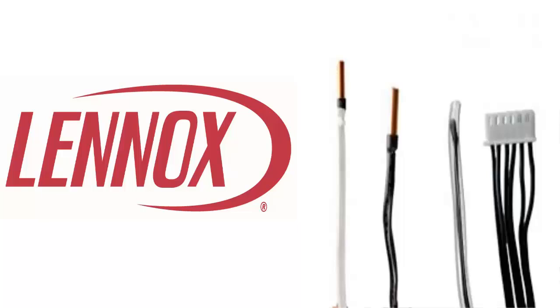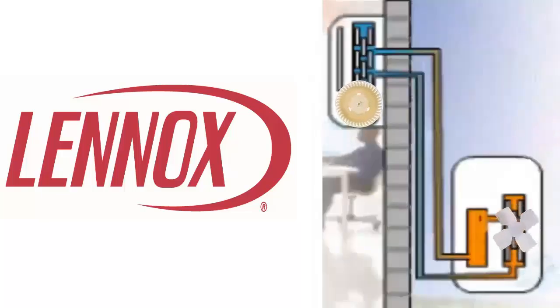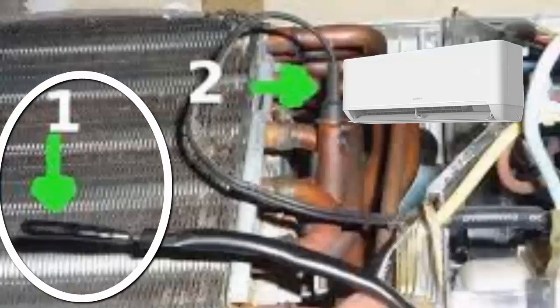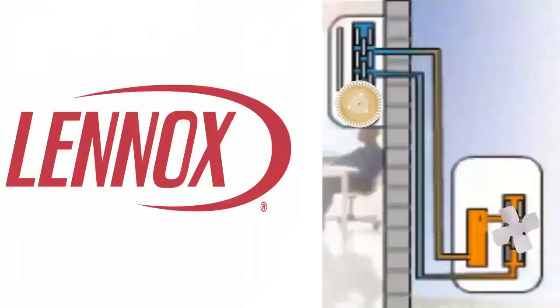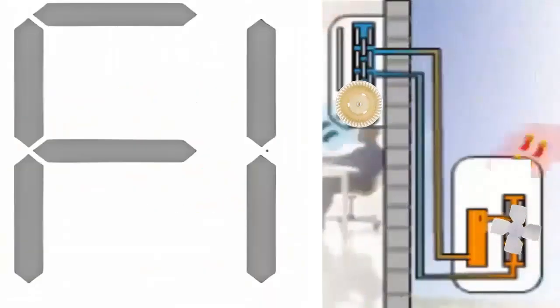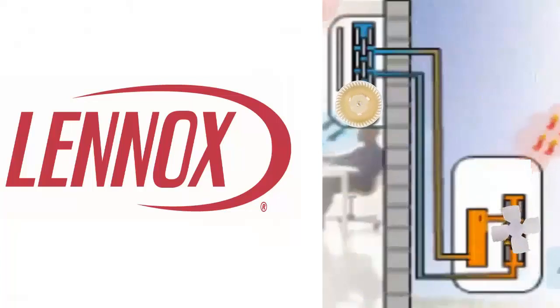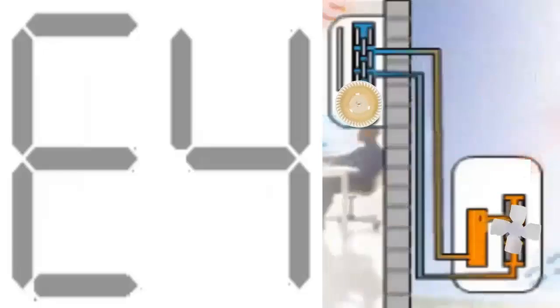Below is the most common interpretation for error codes associated with temperature sensor failures in LENNOX air conditioners. Code F1 indicates an error in the indoor ambient temperature sensor located in the indoor unit. This sensor is responsible for measuring the temperature of the air being drawn in by the fan in the indoor unit in order to average the temperature of the space to be conditioned. Some LENNOX models may also display code E4 in this condition.